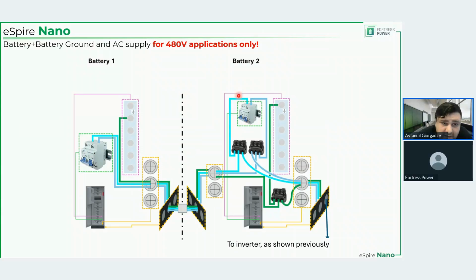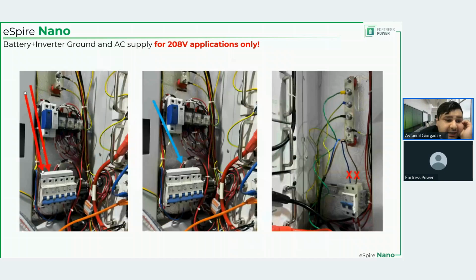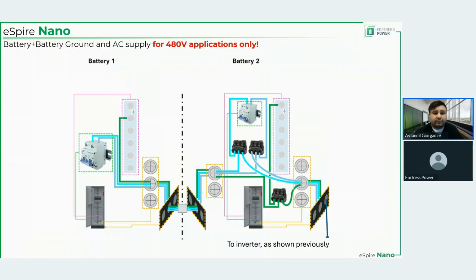That's why it's the right side breaker, just like you see right here. If it's 208 volts, again, you use the same approach as before. So you still have this Polaris connector, but instead of the breaker on the right side, you connect the AC supply to the Polaris, and the Polaris then connects to this breaker on the left on the first battery and on the second battery. If you have a third battery, rather than a 3-port, you're going to use a 4-port Polaris connector, but you will split the main supply, 2 lines, into 1, 2, or 3 batteries, however many you have, and the same applies to the ground, right?